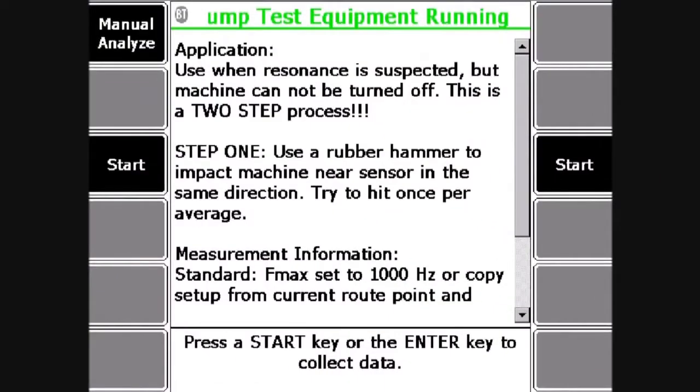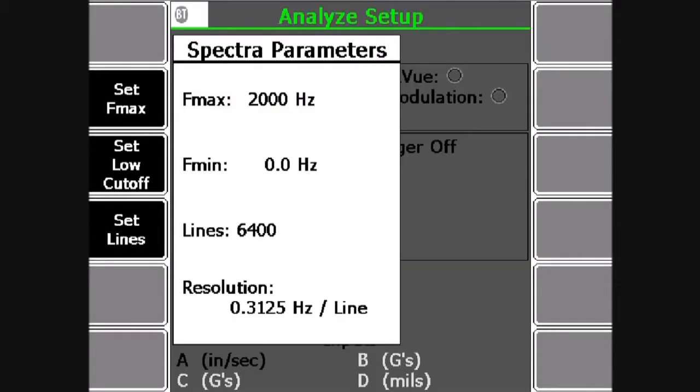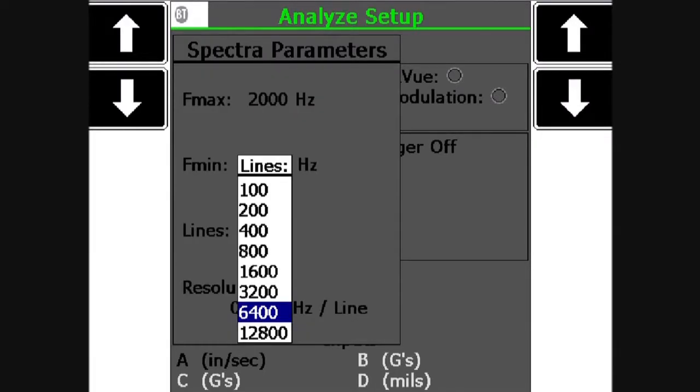Now I'm going to press F1 and adjust my setup here. My F max is 2000 Hertz. My lines are 6400. So I'm going to press F2. I'm going to lower my number of lines here. I don't need that much resolution. I'm going to take it up to 800.